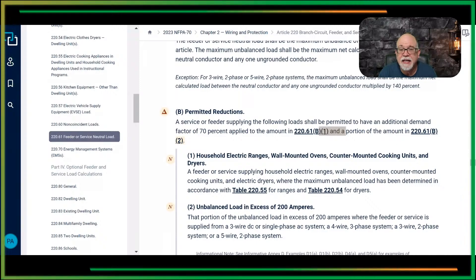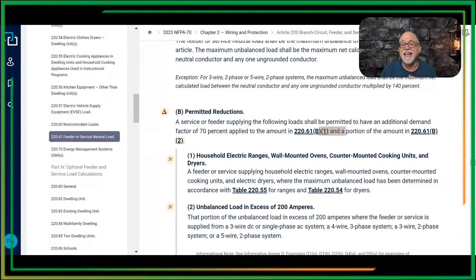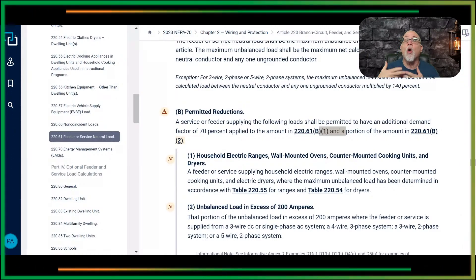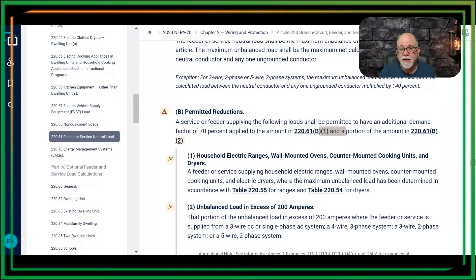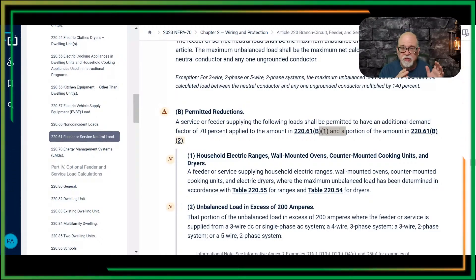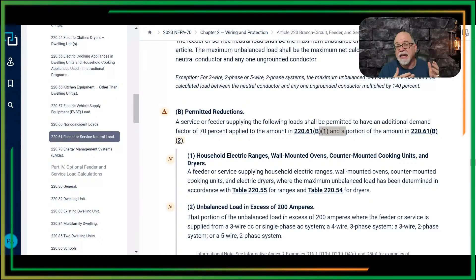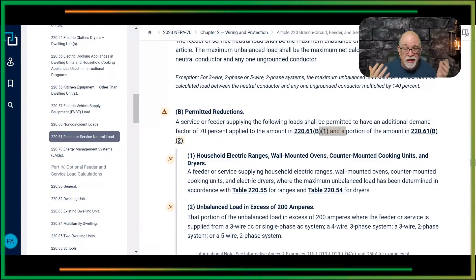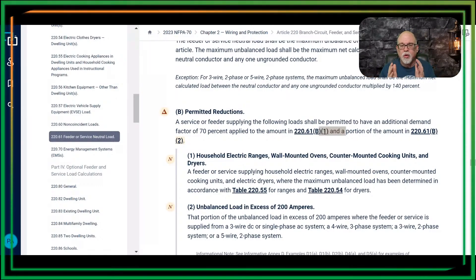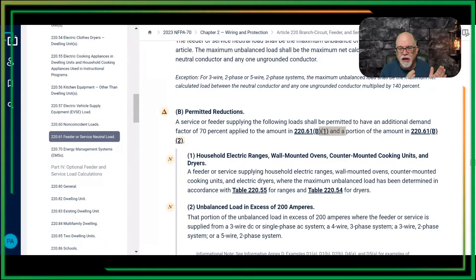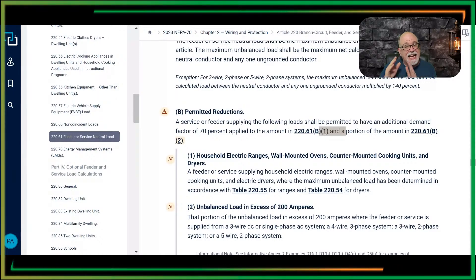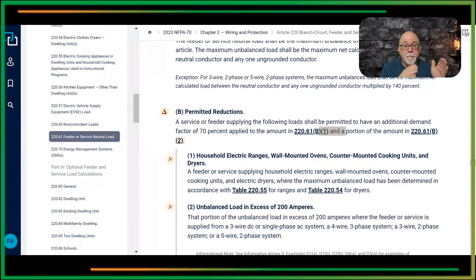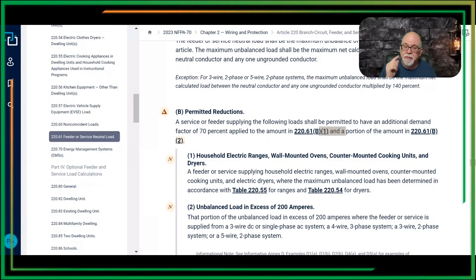The AND is really important because if you're taking an exam, I might give you a question where the total neutral contribution is over 200 amps — even after you've already applied the 70% to the range, ovens, cooking units, cooktops, and clothes dryers. I might still have a neutral load exceeding 200 for exam purposes. You need to know that in the 2020 you can't do it if you've already applied it to the cooking appliances and clothes dryer — you can't apply it to the amount over 200. Whereas in the 2023 you can apply both B1 and B2, because of the AND.